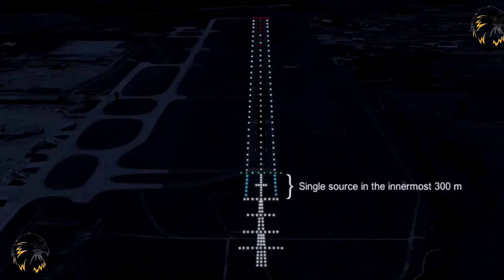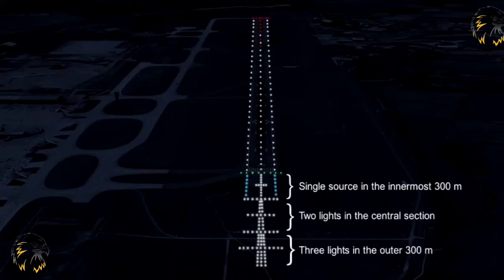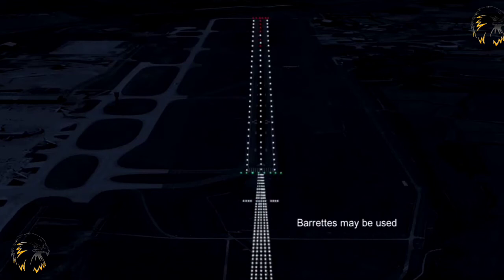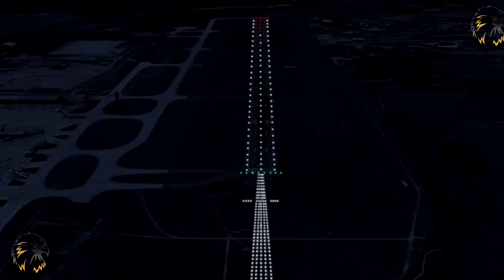Each centreline light shall either be a single source in the innermost 300 metres, two lights in the central section and three lights in the outer 300 metres, which will provide distance information. Barrette lights may be used and be of at least 4 metres in length. If the centreline lights consist of barrettes, they may be supplemented by a capacitor discharge light that will flash twice a second in sequence beginning with the outermost light progressing towards the threshold to the innermost light. They will be capable of independent operation.